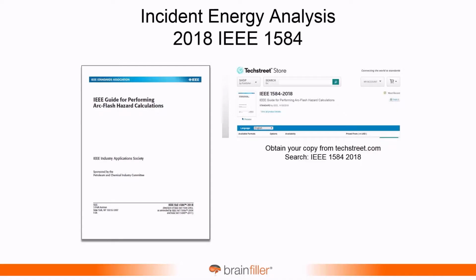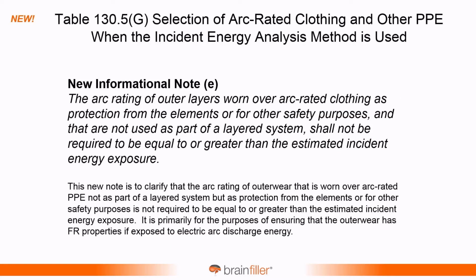Now, why am I talking about this? Because there were some changes along the way. Some of these changes, there was an informational note that was added. So what we have is table 130.5(G), and this is actually for selecting PPE when the incident energy analysis method is used. There's a table for selecting PPE, and I'm going to show you an excerpt of it. There were two changes made to that table. Similar changes were made to the NFPA PPE category table. So both have this similar kind of change.